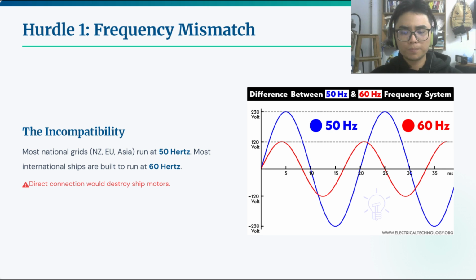This incompatibility is strictly regulated by the IEC/IEEE 80005-1 standard for utility connection. If you were to simply plug a 60 Hz ship into a 50 Hz port socket, the ship motors would run 17% slower, the cooling fans would fail, the equipment would overheat, and the ship electronics would be destroyed.